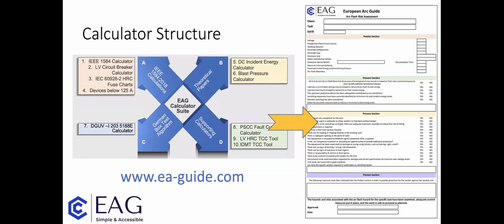And then in B, arrow B, we've got theoretical papers, and there's a calculator there for calculating the incident energy for DC, and also blast pressure. Within C, there's the German algorithm, which is based upon the box test. It's an IEC box test within Europe, which is the DGUV standard. And there's a calculator in there to provide support for that. And then to support all the other calculators, the prospective short circuit fault current calculator. There's a tool for looking at the HRC time current curve, and also an IDMT tool as well.